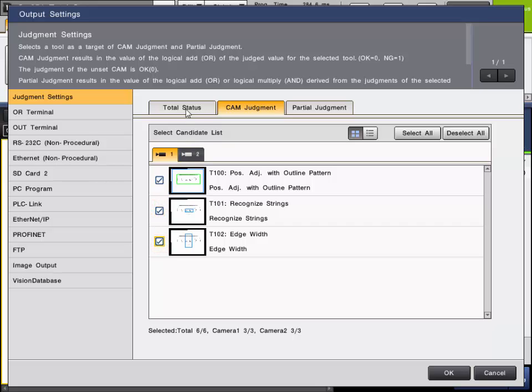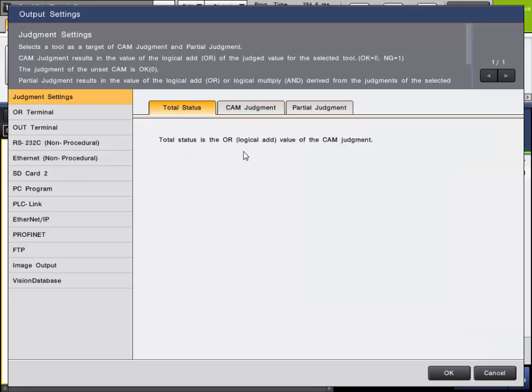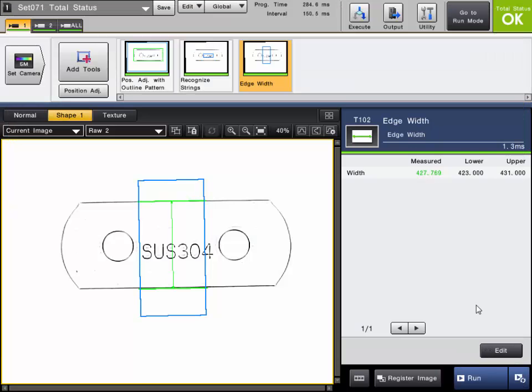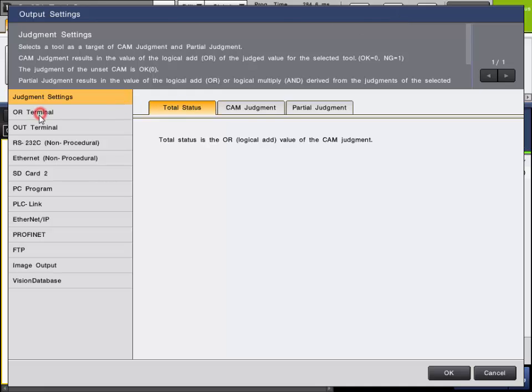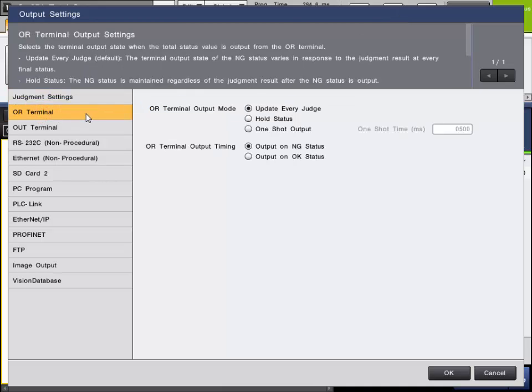Otherwise, the total status will just logically OR all tools altogether. Next, we can set the behavior of how the OR output itself will operate. From the output menu, click the OR terminal setting. That's the output on the terminal block directly linked to the total status. There are three modes the output mode can be set to: update every judge, hold status, and one shot output.